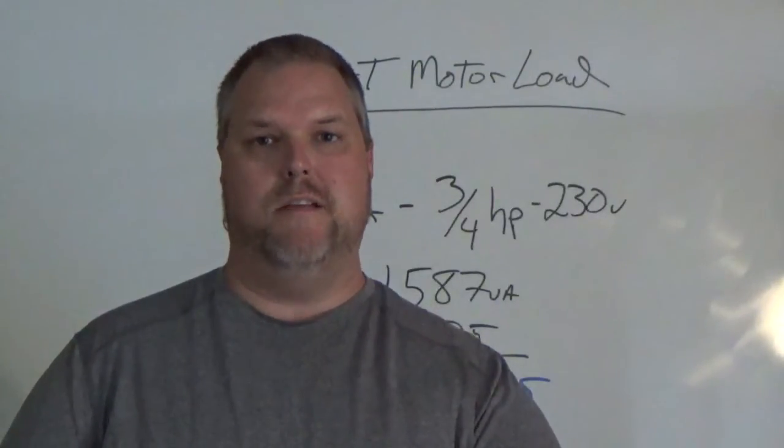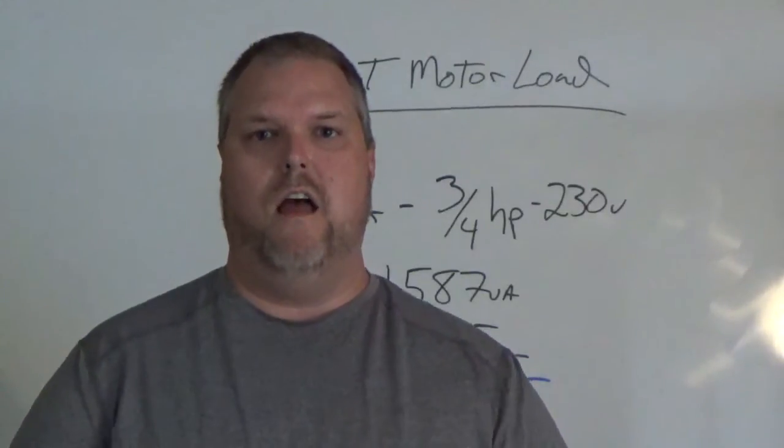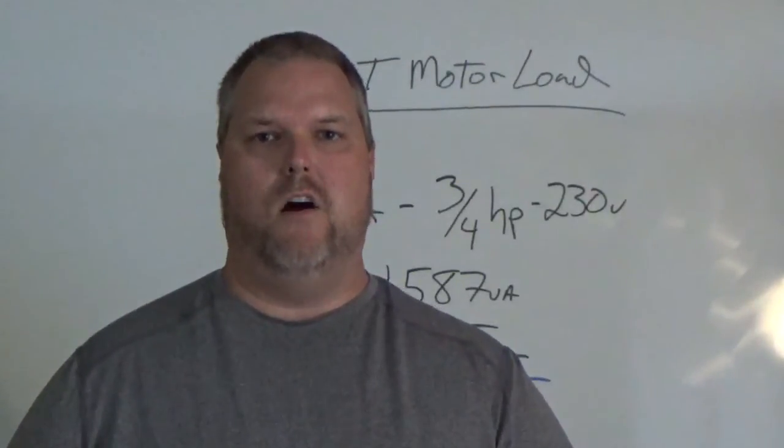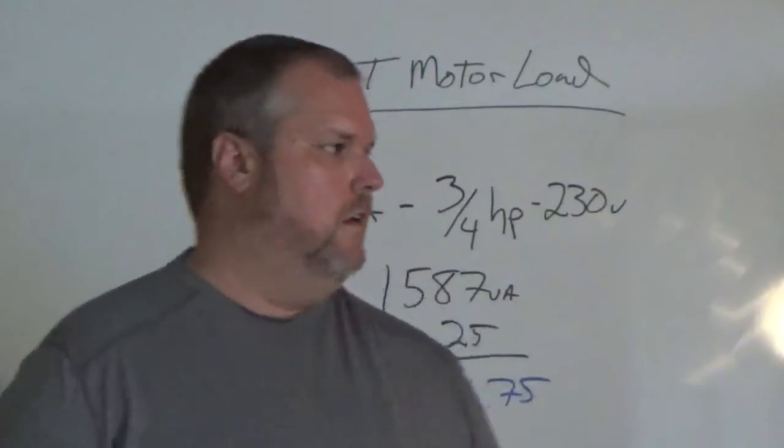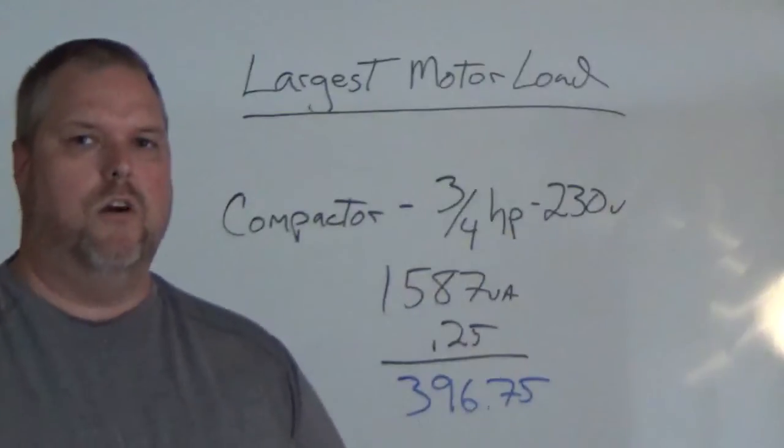What we have to do now is multiply that by 25 percent, because remember, the largest motor has to be taken at 125 percent. Every motor after that is taken at 100 percent. 396.75 will go in line 14.